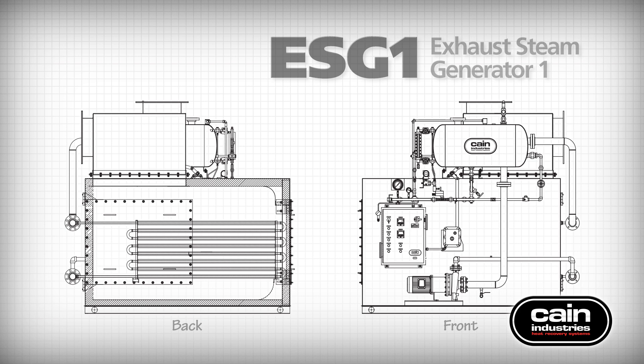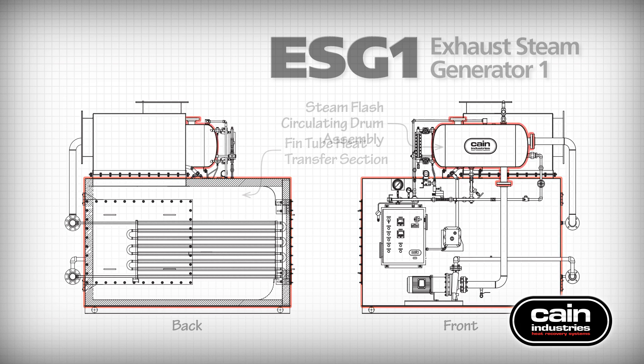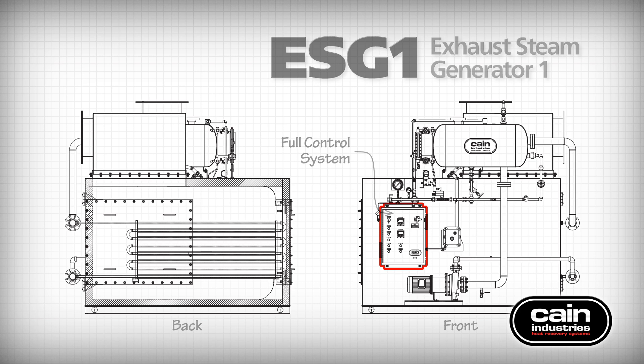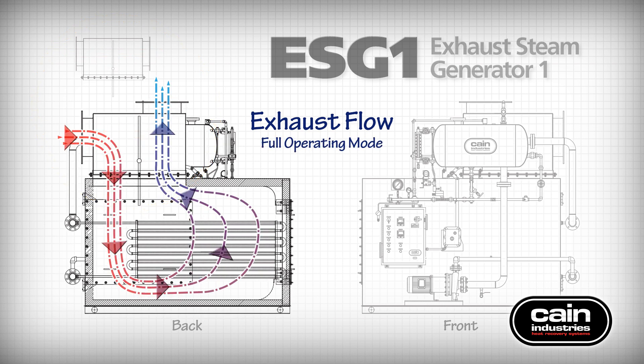Each ESG-1 includes a modulating exhaust gas bypass, fin tube heat transfer section, steam flash circulating drum assembly, and full control system and boiler trim for a complete skid-mounted solution. Cain Industries' exclusive exhaust bypass is used to modulate exhaust gas flow depending on steam production requirements. Full bypass mode diverts exhaust gas away from the heat transfer section. The bypass can be configured as horizontal, straight through, or a 90-degree vertical exhaust connection depending on installation requirements. Full operating mode directs the exhaust gas into the heat transfer section, through the modular fin tube racks, and exits back through the bypass.